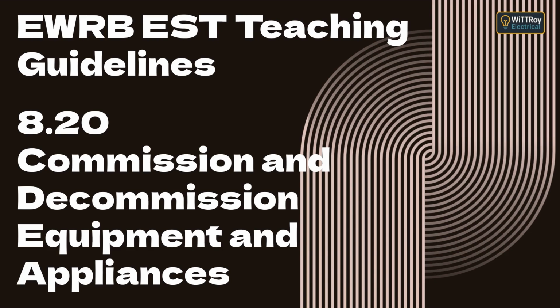5. Flexible cords and cables, found on portable appliances. Ensure the outer sheath is gripped, the conductors are not strained, and the earth is the longest conductor so it's the last to break if pulled. 6. Cables and conduit, whether metal or PVC, check that glands and bushings are fitted correctly and that earth continuity is maintained through metallic systems. 7. Copper-braided sheath flexible cables, used in welding and special tools. Inspect for frayed braid and ensure the braid is correctly earthed at terminations. Each type has its own hazards, so understand the construction and always re-terminate exactly as designed.